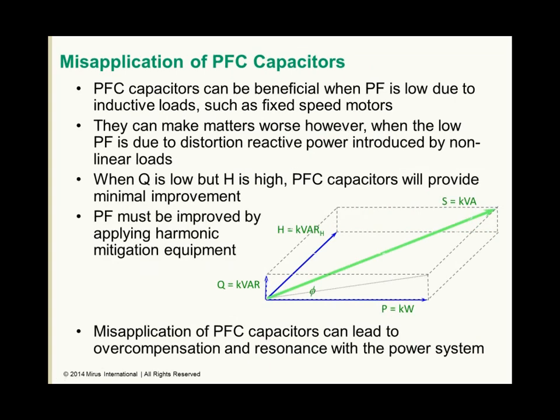The problem is power factor correction capacitors are often misapplied these days because the low power factor is the result of harmonics introduced by nonlinear loads rather than the inductive reactive power introduced by fixed speed motors. So here in this vector configuration, we have a fairly small Q, or inductive component in kVAR, but we have a quite large H, which is our distortion component. This is very typical of nonlinear loads. In fact, this is often much smaller than I'm even showing here.